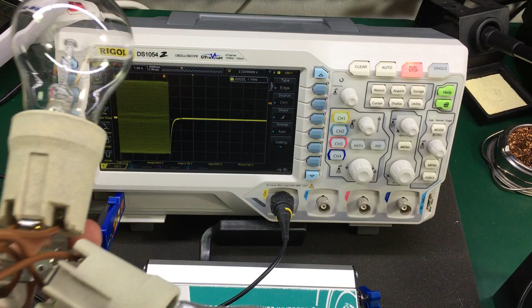If the fan starts, if the enclosure starts to get hot - everything that needs to be tested under load. We can also measure the efficiency of the inverter by measuring the input voltage and current and the output voltage and current. We can calculate the difference between the input and output power, and so we obtain the efficiency of this inverter.